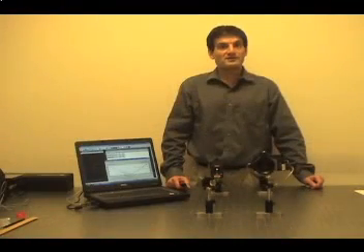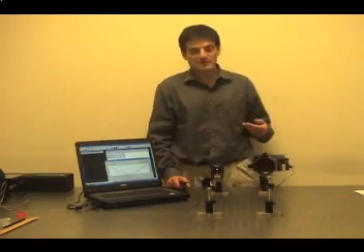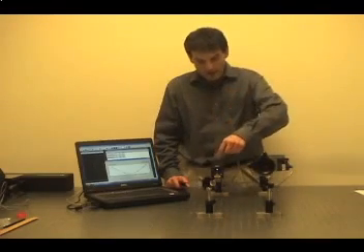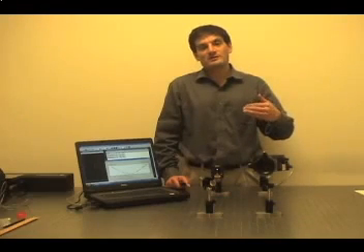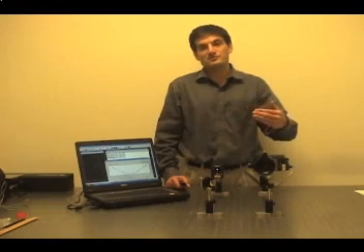Now that we've used the 1780 mode scan calculator to set up our test, I've set it up here on the bench. I'm using turning mirrors which I don't need to use, but I'll show you a little bit later it's very convenient to use them.